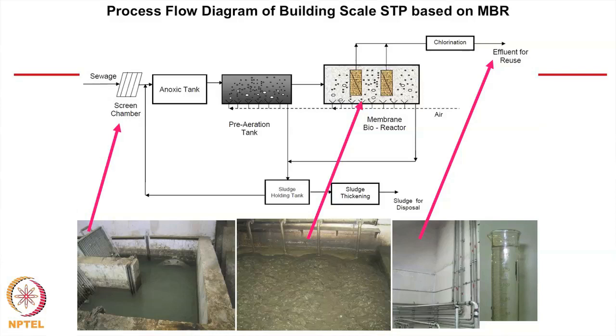Just look at the scheme, and then you have this particular plumbing system, twin plumbing system or double plumbing system, which takes care that recycled water will be used for toilet flushing. So these plants can be designed and operated, and this can be effective because it will reduce the freshwater demand of the entire building, because toilet flush is about 40 to 50 liters per person in such a lifestyle. So that much fresh water consumption will reduce. So this is for long-term sustainability of the city.